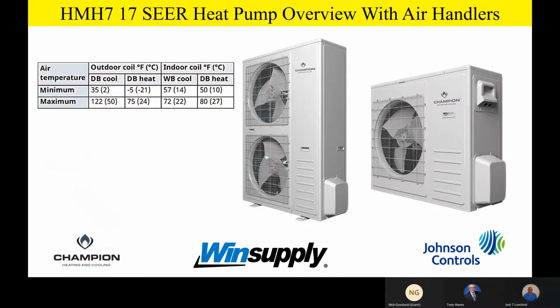Another thing we like to talk a little bit about is we get a lot of questions concerning what the capacity of the unit is at different temperatures. Even though the AHRI rating on these units is at 47 degrees Fahrenheit outside in the heating mode and 17 degrees outside in the heating mode, we have a lot of flexibility here. As a matter of fact, Tony's got some real neat information he can share with you at a later time that shows that these units, even at 0 degrees, are still making about 25 to 40% capacity. And at 47 degrees outside, they're making just about 100% capacity, real close to it. So they're very flexible as far as temperature ranges and lots of capacity. Now, this is going to be important, especially in a straight cool application.